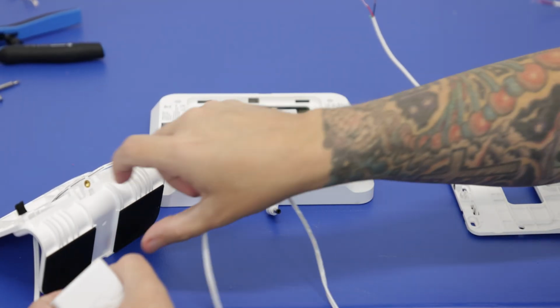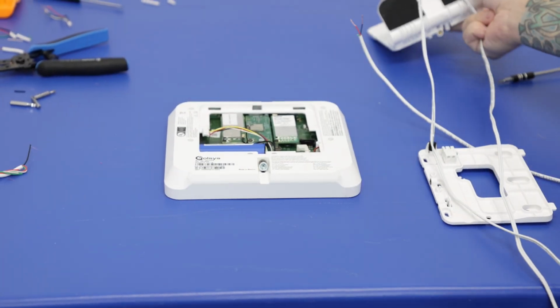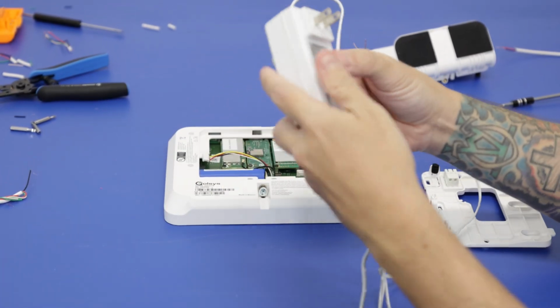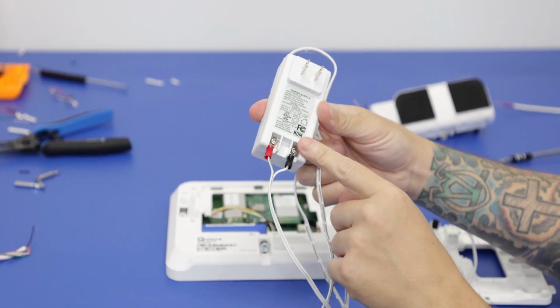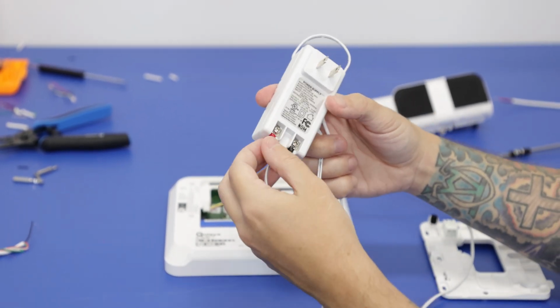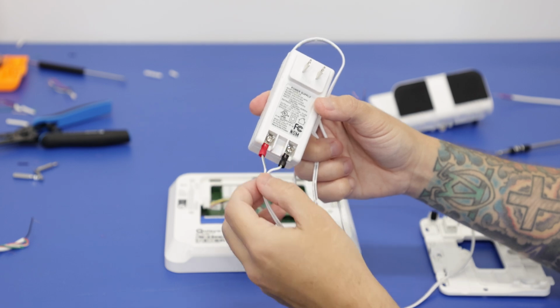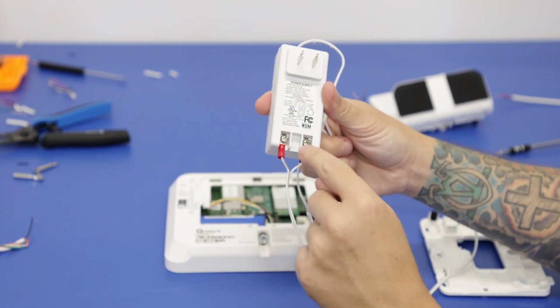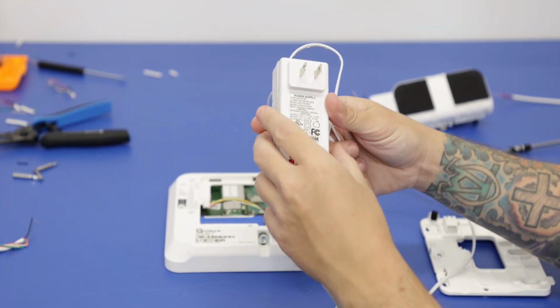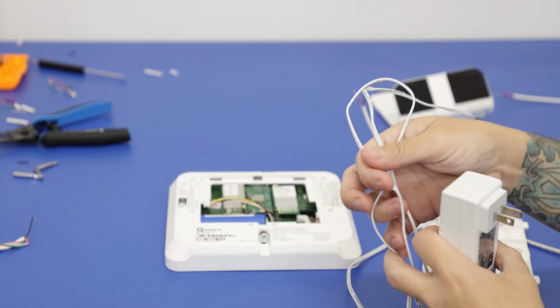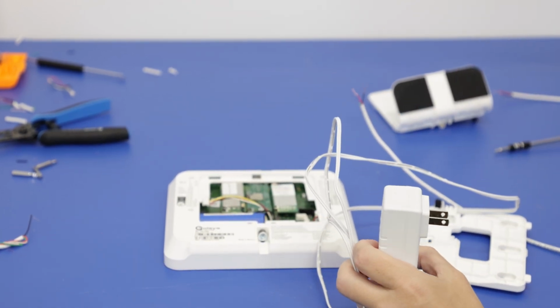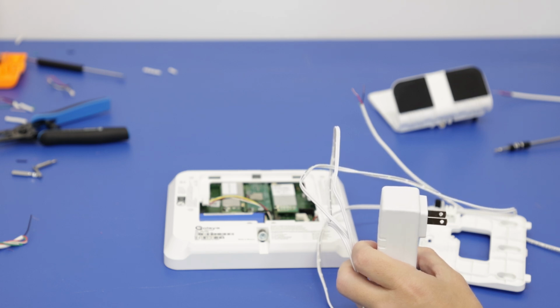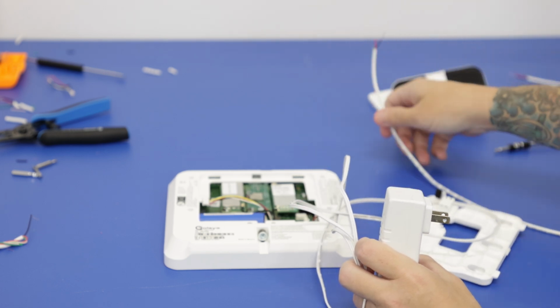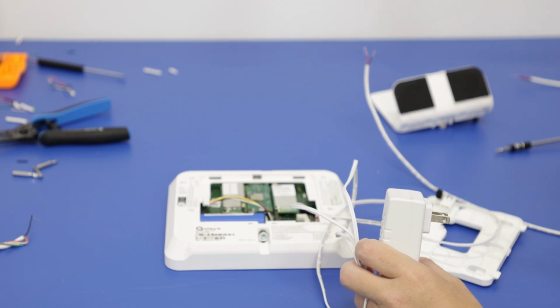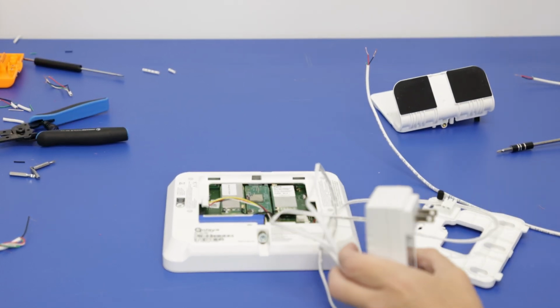And that 10 foot cable goes to the included transformer here. So this is a DC plug, so it does have polarity. So we have our red on positive. And then our black on negative, you'll see the two indicators right there. Now, if you want a wire that's longer than the 10 foot wire, you can use 18 by 2 gauge wiring, which we have here. And that you can run up to about 98.5 feet.